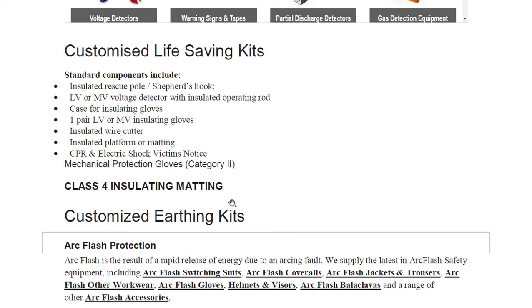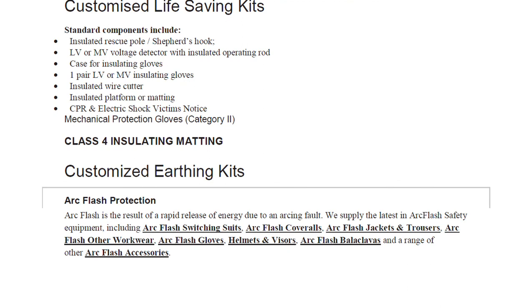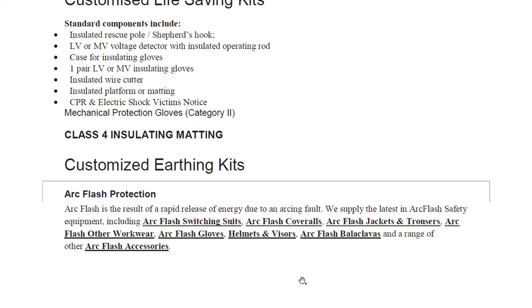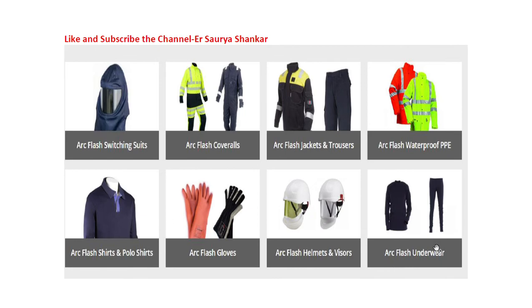Class 4 insulating matting can hold up to 33 kilovolts. There is also a customized earthing kit. Arc flash protection is also important — arc flash is the result of a rapid release of energy due to an arcing fault. Special arc flash safety equipment includes arc flash switching suits, arc flash coveralls, arc flash jackets and trousers, and other arc flash worker protection items.